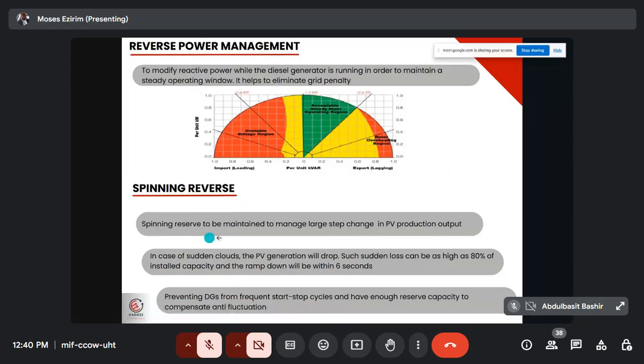Now, spinning reserve. Spinning reserve is to be maintained to manage large step changes in PV production output. What this simply means is that, for example, I'm sure you must have seen a situation whereby you have sun during the day, maybe around 12, and then the cloud just covers the atmosphere. At that point, definitely you will see a drastic reduction in the PV output. All right, but with the spinning reserve function in a controller, it helps to balance it.